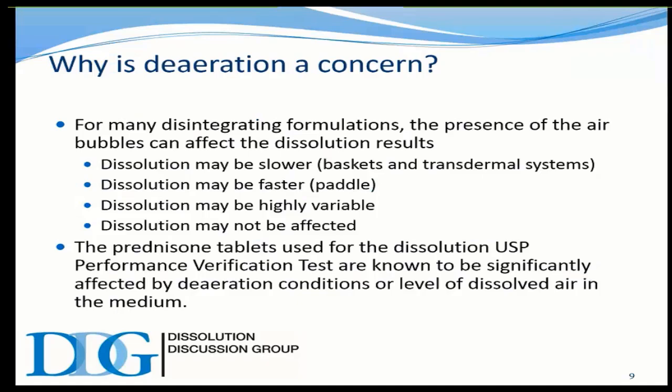Well, think of how many disintegrating formulations that you have. The presence of air coating the vessel wall very often for paddles can increase the dissolution rate. Interestingly, in some different products, it may affect them in a different way. Baskets, because bubbles form in a basket and flow is restricted through a basket, may exhibit some slower results. Same thing may happen on the surface of a transdermal system that's tested with USP apparatus 5 or 6. If bubbles form on the surface of that patch, nothing is moving through right there. So it may suppress dissolution rates for some things.